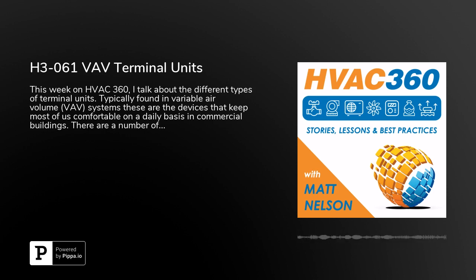A couple other things that are interesting. The electric heater. Now, I've had some issues with electric heaters in the past. Obviously great devices, they work well, and if you don't have the heating hot water, it's really the only way that you have to go. But you have to be especially careful about flows when you're dealing with the electric heat. The minimum flow is going to be critical. There's no way you can cheat on it, and it's just going to be a tripping hazard if you end up cheating on it a little bit. So that's something that you will have to continually wrestle with if you don't get it right.